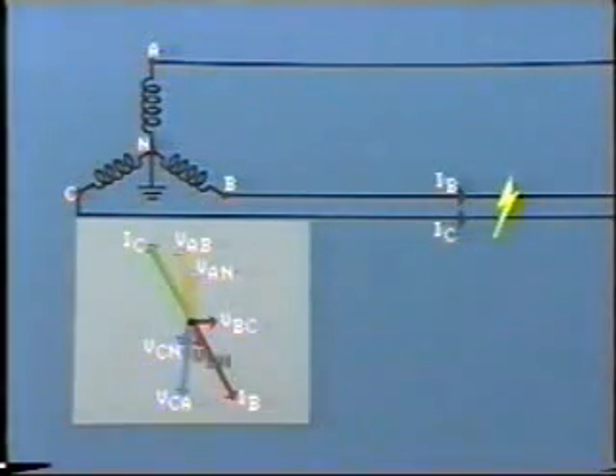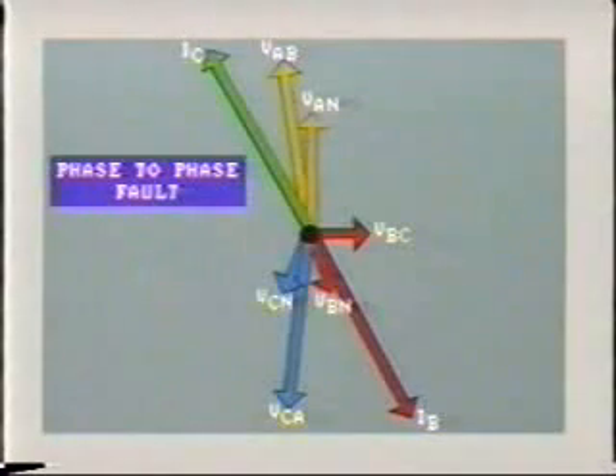Similarly, the voltage between line B and ground would be lower, as is line C to ground voltage. The phasor diagram shows this. The short circuit drastically reduces the difference in voltage between lines B and C, that is, VBC. This reduces phase voltages VBN and VCN, and the angle between them to less than 120 degrees. This causes a change in the phase relationship of VAB, which is the voltage between the lines A and B.